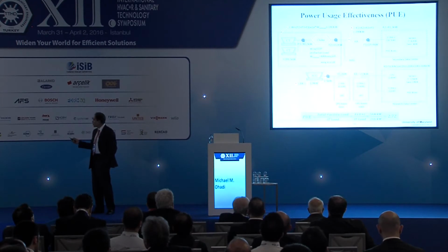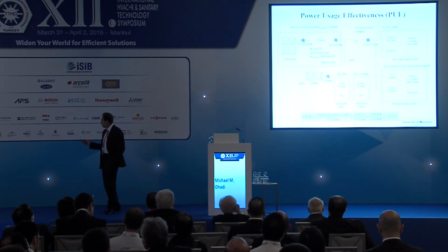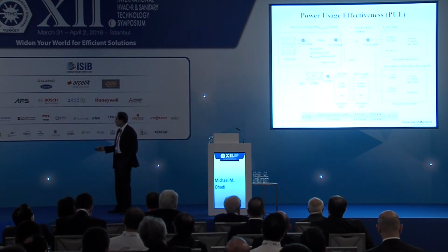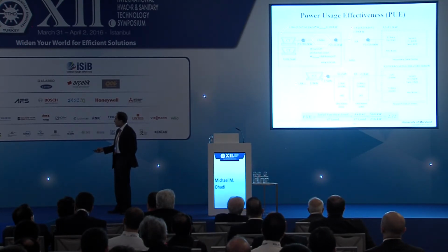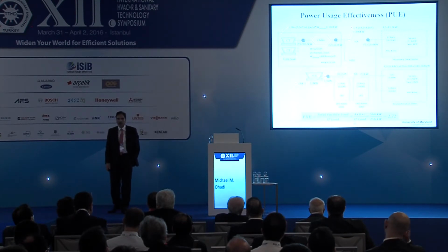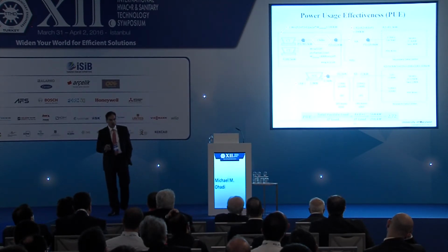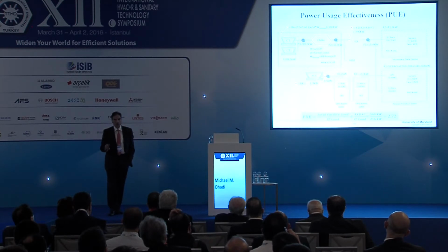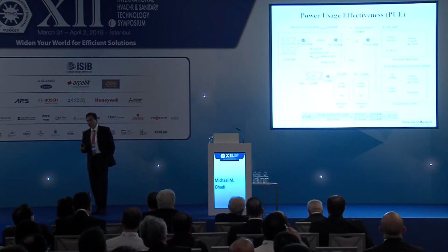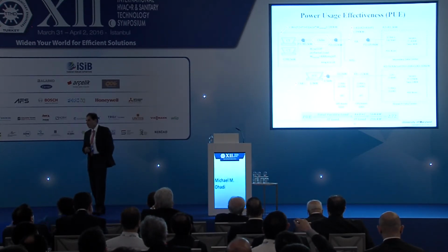This shows one typical example of how we calculate the PUE. We measure the total power coming to the data center, add it up, and divide by the amount of power that goes into the IT devices. So if you have a PUE of 2.72, that means you're consuming potentially 3 times more power than the ideal situation.